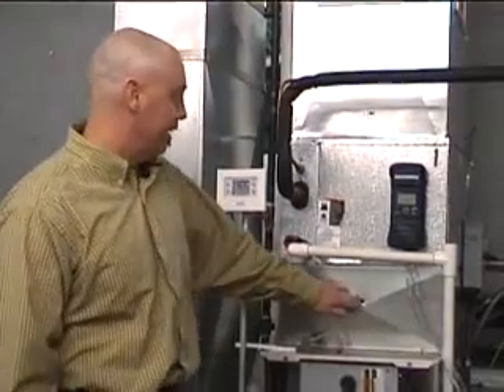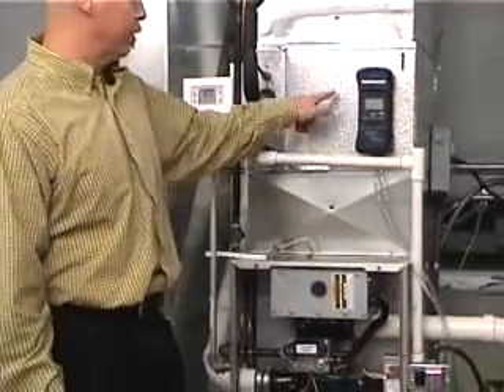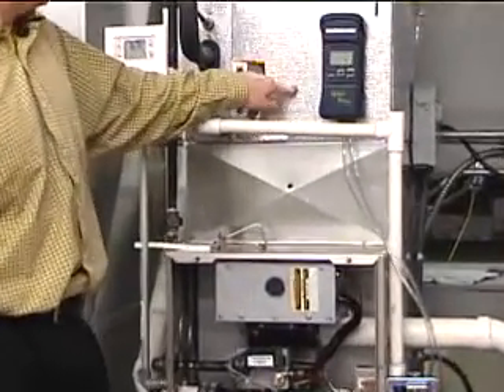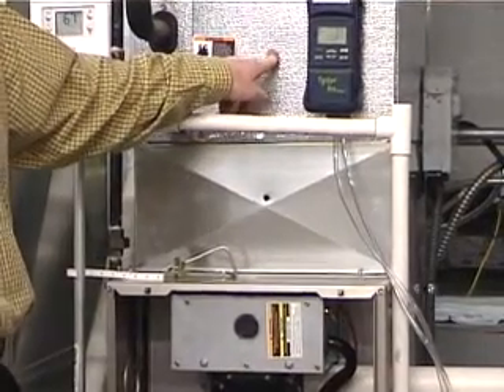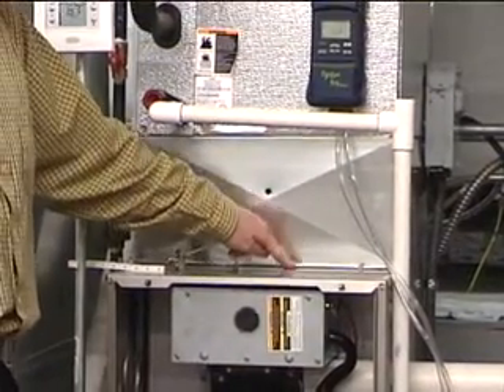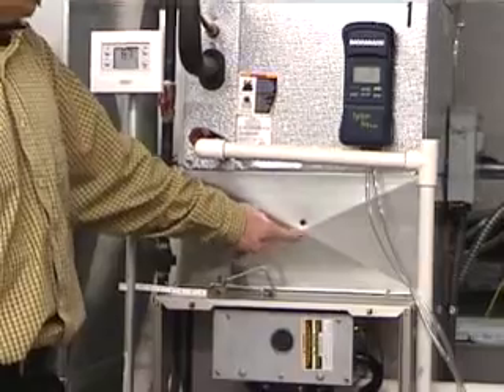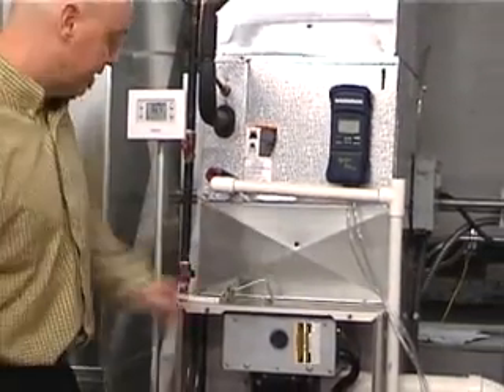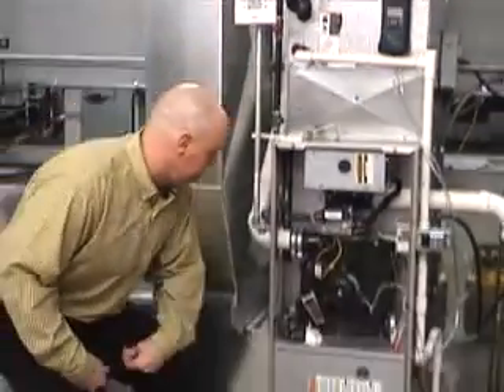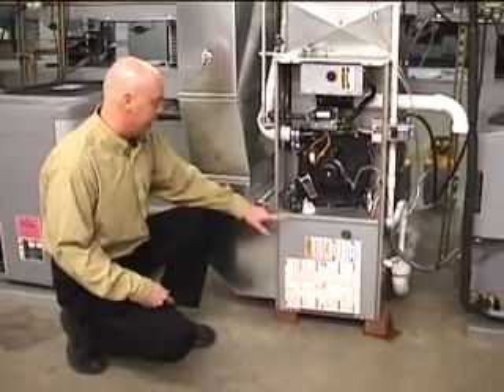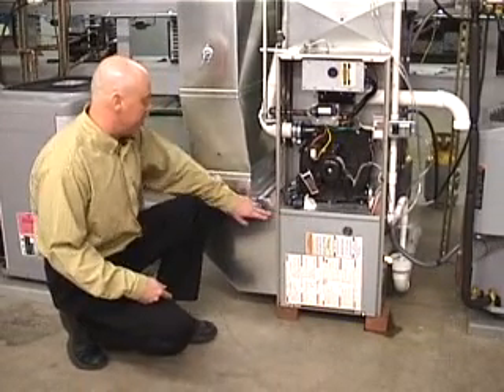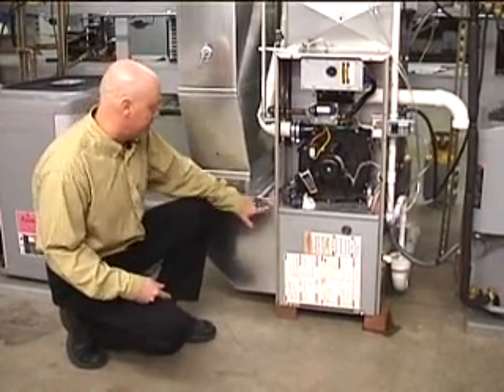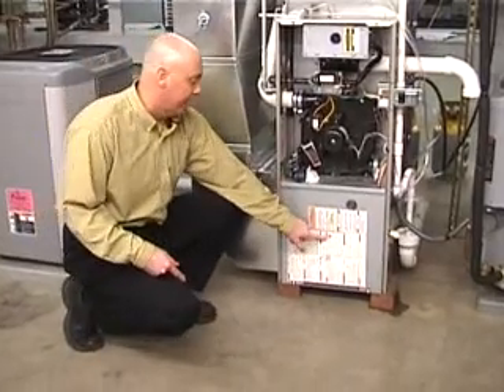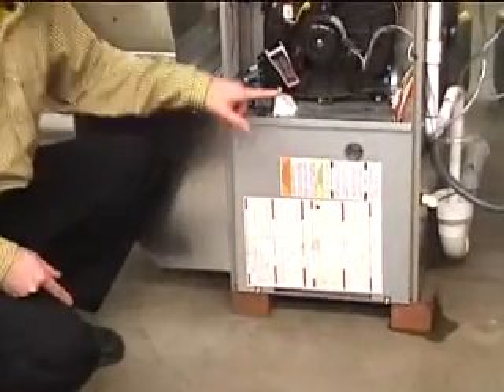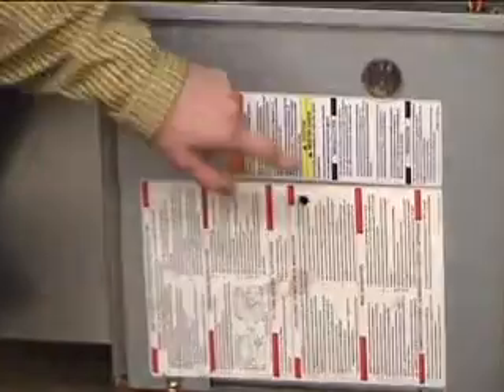One hole you have to have is between the furnace and the first piece of resistance. Typically, that first piece of resistance is an A coil if you have air conditioning. So you actually have to be between the furnace and the coil. So that is the first hole that you would have to make. The second hole you would have to make is between the filter and the furnace. You have to be between these two and not on this side. So you have to be between the filter and the furnace. A lot of times you can access that right through the blower door, as long as you have a good seal on the blower door itself.